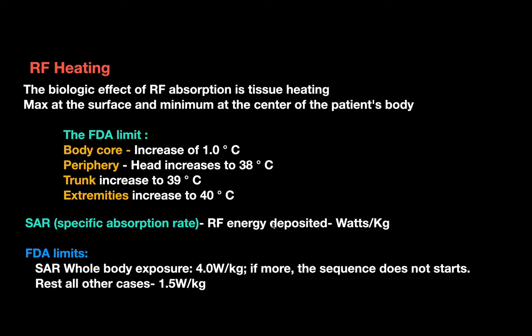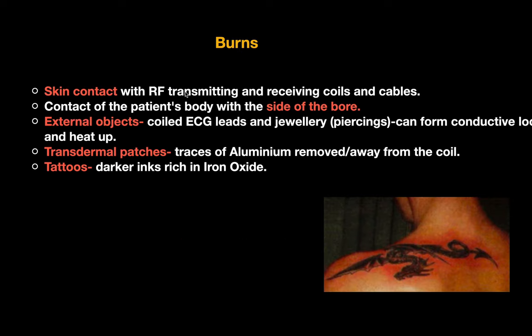The Specific Absorption Rate (SAR) depends on the radiofrequency energy deposition in the body and is measured in watts per kilogram. FDA limits are: for whole body exposure the maximum is 4 watts per kg — if exceeded, the sequence will not start. For all other cases, 1.5 watts per kg is acceptable.